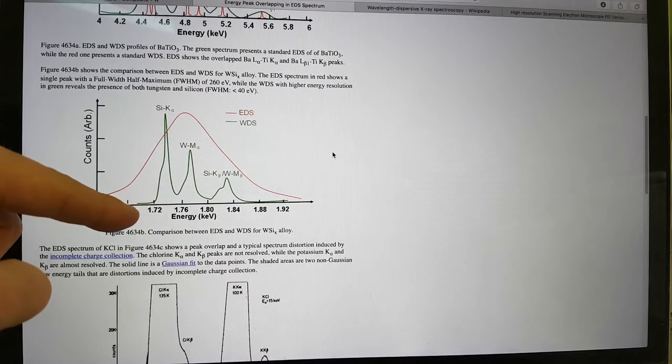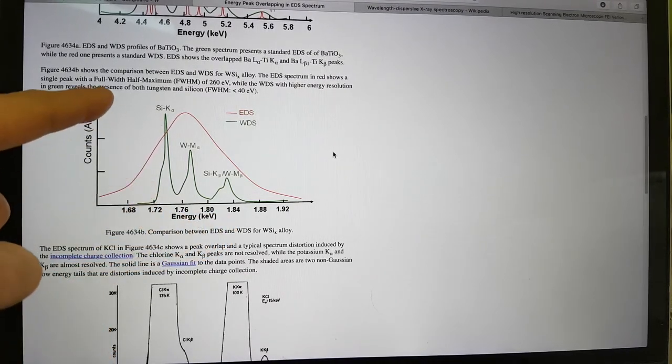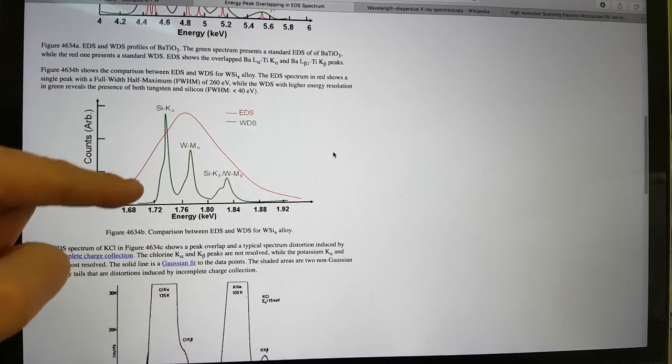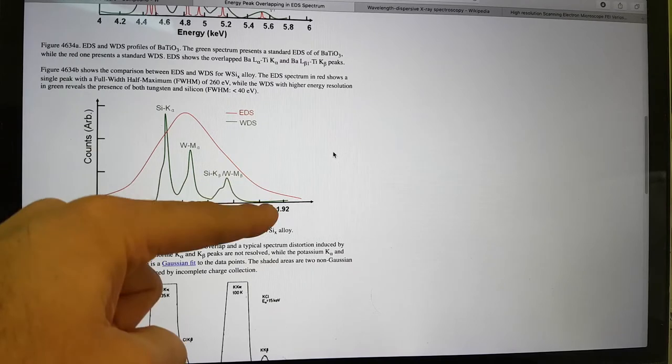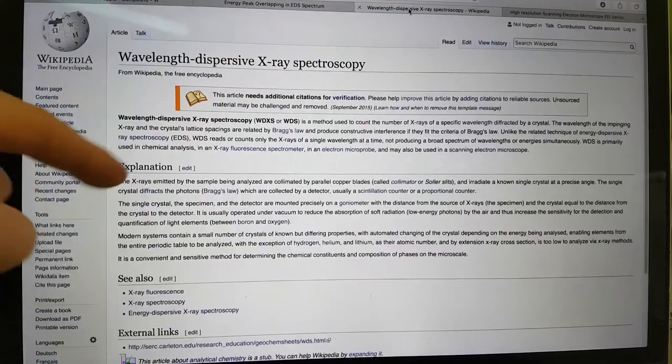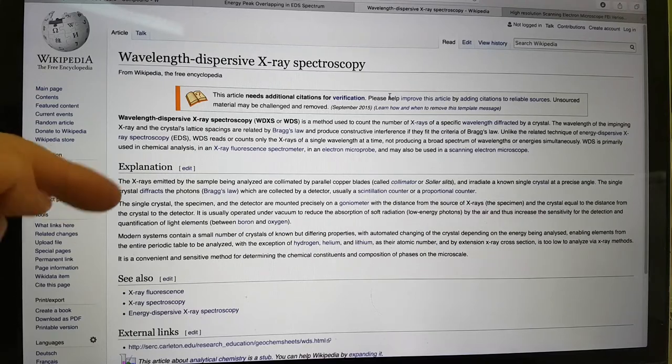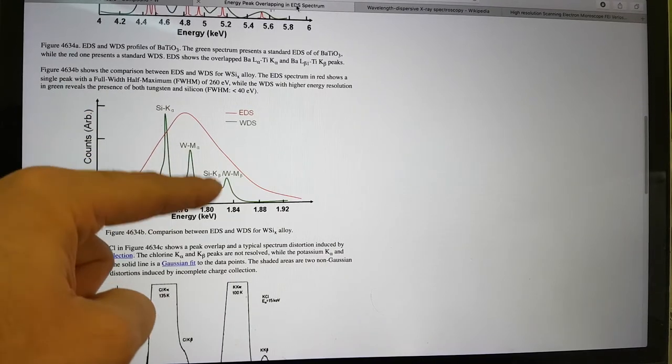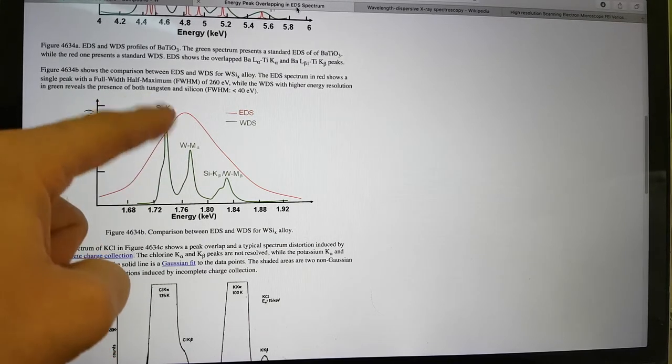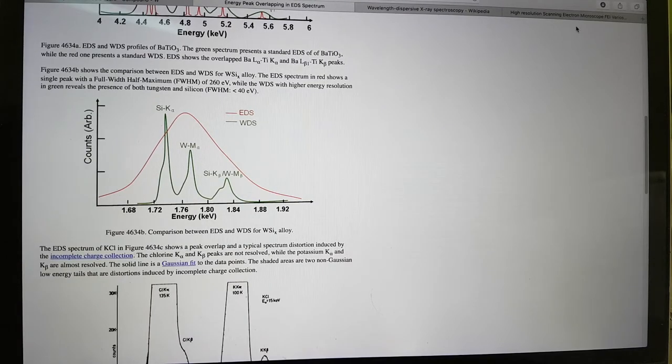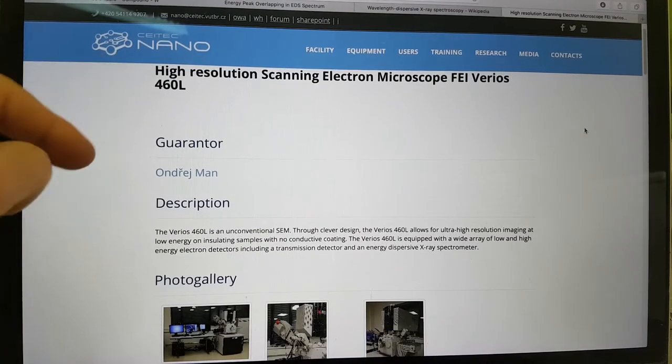And it's interesting because it actually gave the silicon and tungsten overlap peaks as a classic example. And here we can see that in EDS, with the compound tungsten-silicon alloy, which is one of the alloys, the full-width half-maximum FWHM on EDS spans across the silicon and tungsten various peaks.